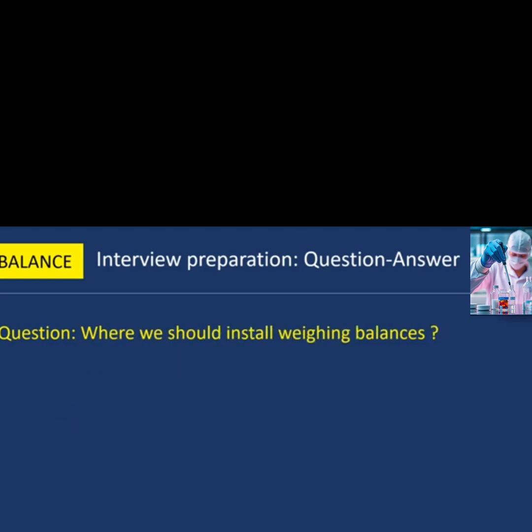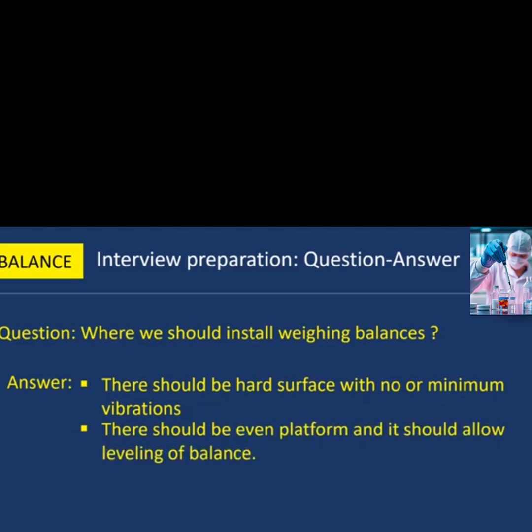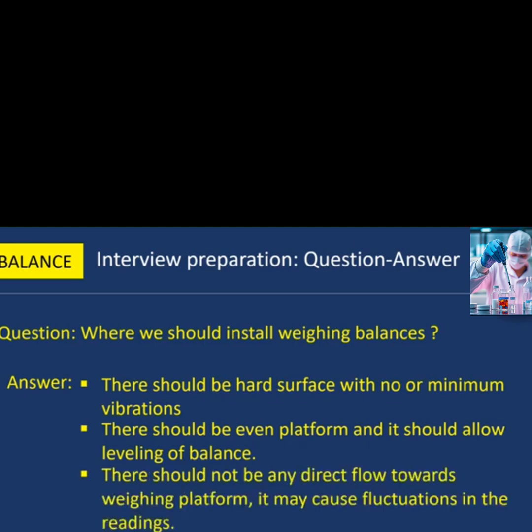Next question: where should we install weighing balances? The following points should be considered while installing weighing balances. First, there should be a hard surface with no or minimum vibrations. Second, there should be an even platform that allows levelling of the balance. Third, there should not be any direct airflow towards the weighing platform, as it may cause fluctuations in readings.